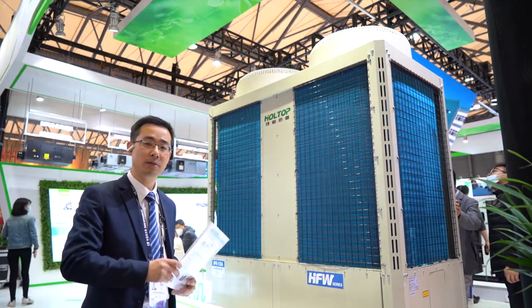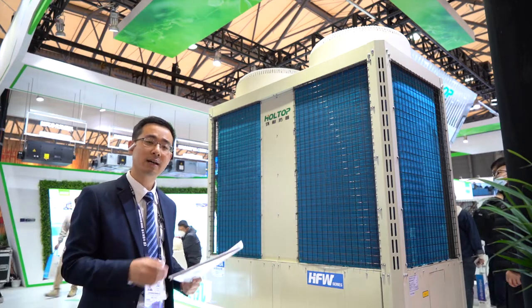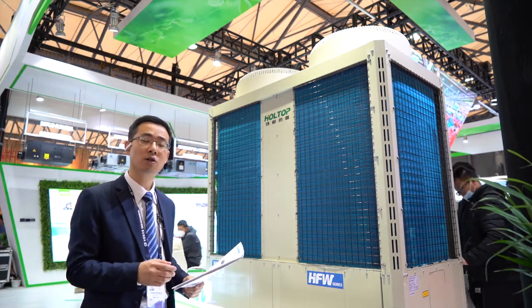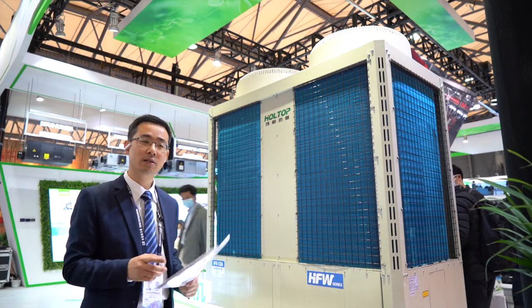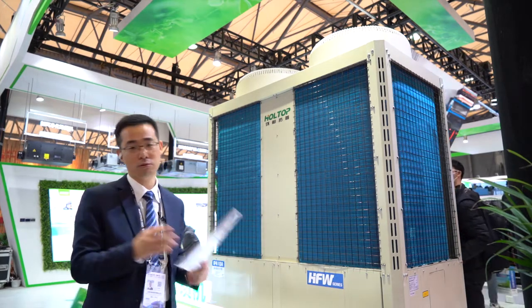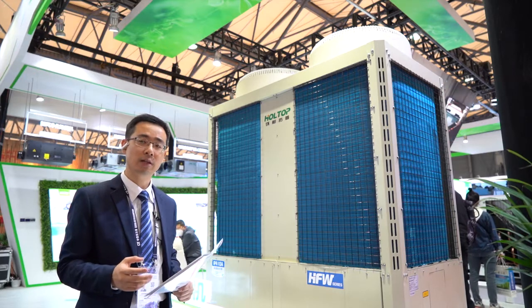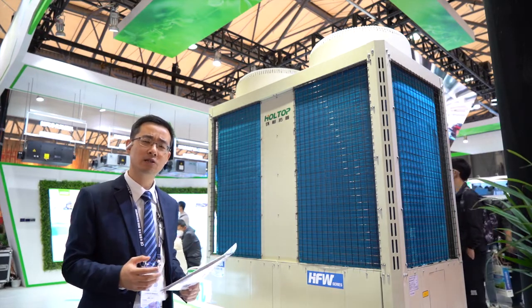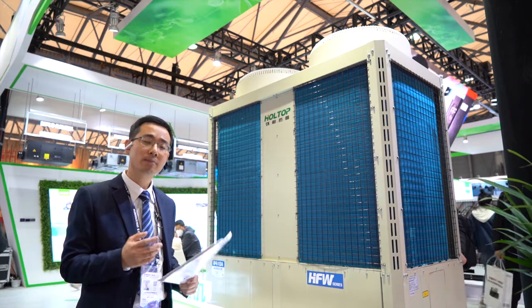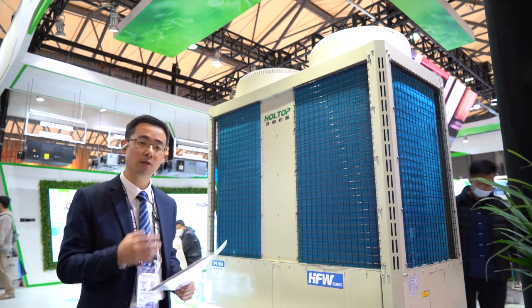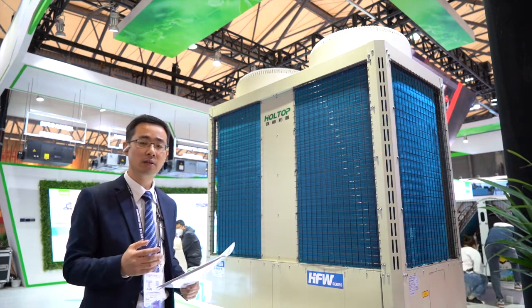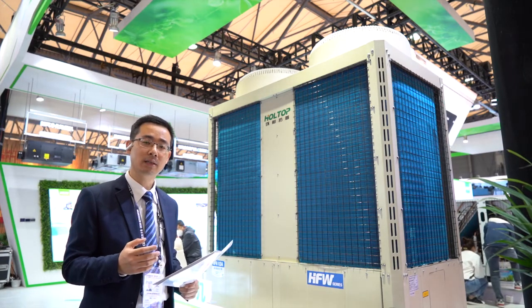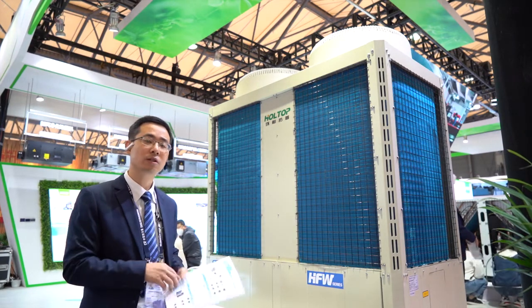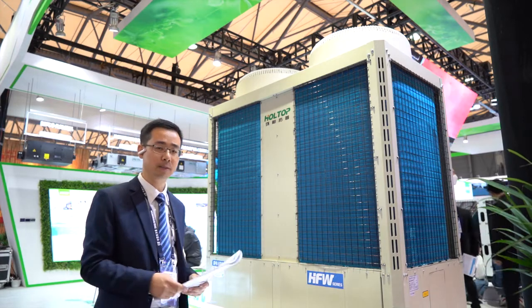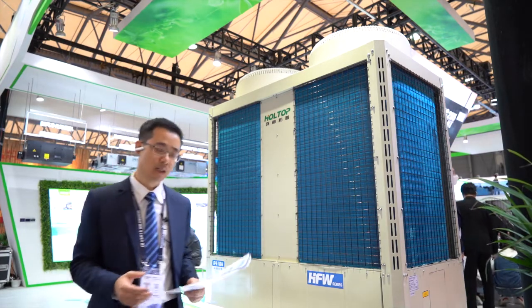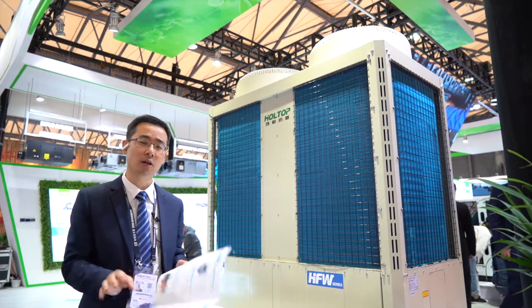And finally, it will be the heat exchanger. This kind of heat exchanger is called a tube-in-shell type heat exchanger. It is for heat exchange from refrigerant to treated water. And this kind of heat exchanger can be more than 10% more efficient compared to the general tube type heat exchanger. Okay, so this is the main components of our water chiller. And next, I'm going to talk about its operation.